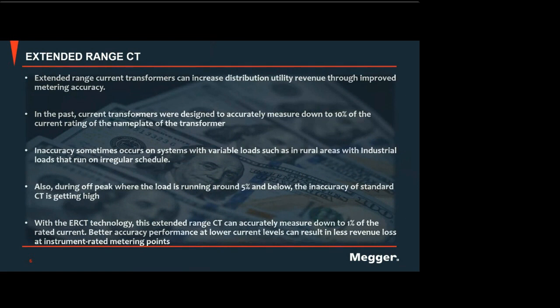In the past, CTs were designed to accurately measure down to 10% only. Okay? And there was inaccuracy, of course, on systems with variable loads. So for example, if you have factories, industrial parks, and they turn off some of their motors, of course they will have this low load, and that is where the inaccuracy starts. Also during off-peak, where the load is running around 5% only, the inaccuracy of a standard CT gets high. With the ERCT technology, I'm not promoting ERCT here, but I just want to explain it to you. This extended range CT can accurately measure down to 1%. Please take note of this, down to 1%. They are very, very accurate.